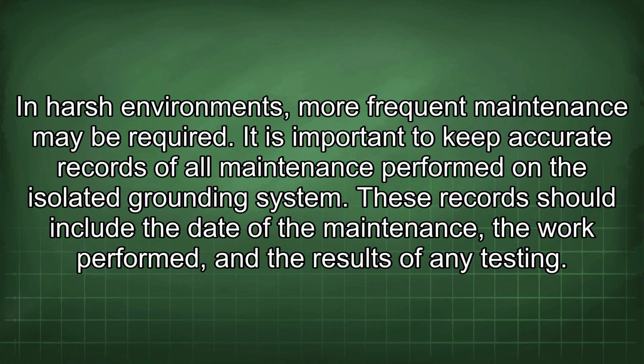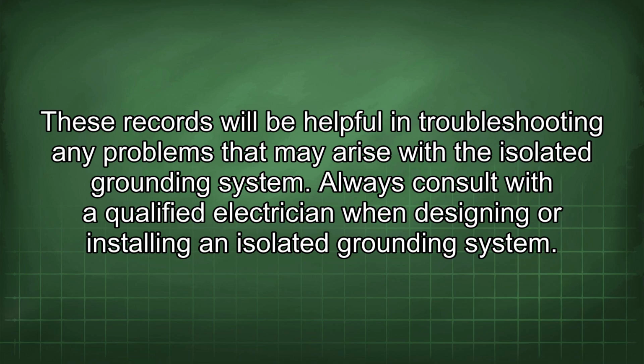It is important to keep accurate records of all maintenance performed on the isolated grounding system. These records should include the date of the maintenance, the work performed, and the results of any testing. These records will be helpful in troubleshooting any problems that may arise with the isolated grounding system.